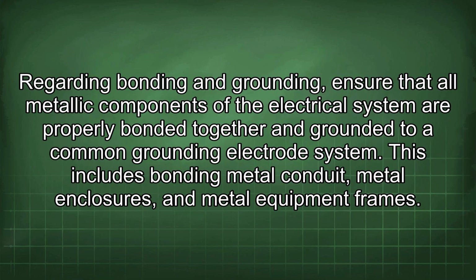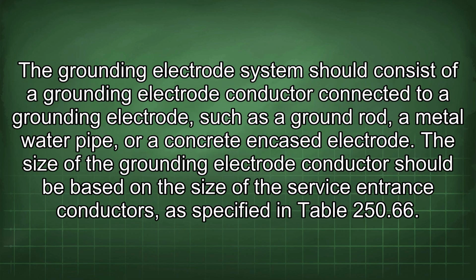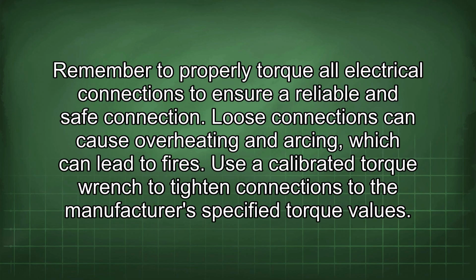Regarding bonding and grounding, ensure that all metallic components of the electrical system are properly bonded together and grounded to a common grounding electrode system. This includes bonding metal conduit, metal enclosures, and metal equipment frames. The grounding electrode system should consist of a grounding electrode conductor connected to a grounding electrode, such as a ground rod, a metal water pipe, or a concrete encased electrode. The size of the grounding electrode conductor should be based on the size of the service entrance conductors, as specified in Table 250.66. Remember to properly torque all electrical connections to ensure a reliable and safe connection.